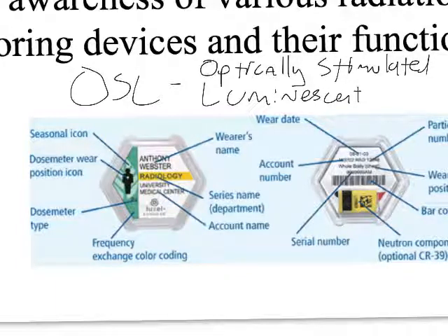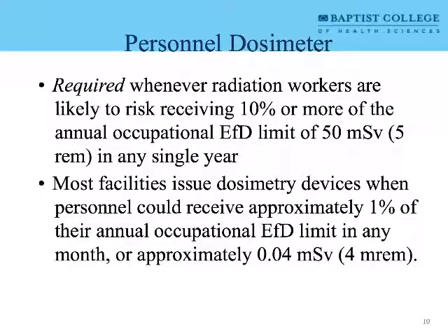The main thing that we use them for are for personnel monitoring, and we use a monthly or bi-monthly report to track people's exposure. This monitor does not indicate to me immediately whether or not I've been exposed to radiation, like whether I'm being exposed right now. I have to wait a month or two, and then I get my report back, right? So in addition to having monitoring like this, we also need monitoring like Geiger counters and things like that.